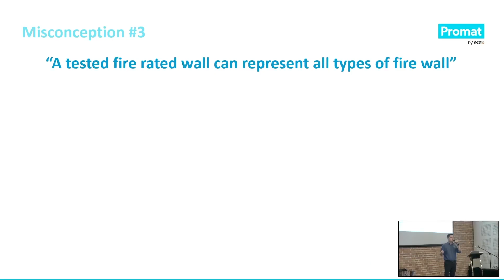Bear in mind, different construction, different types of wall behave differently during a fire. You can have the normal infill with mineral wool and some layers of boards, then some walls without mineral wool, then some with a combination of corrugated metal, then some composite cement boards. All of this gives a different reading when you do a fire test on it—the fire rating is different.